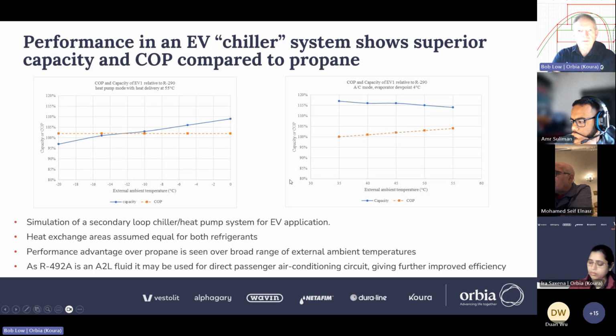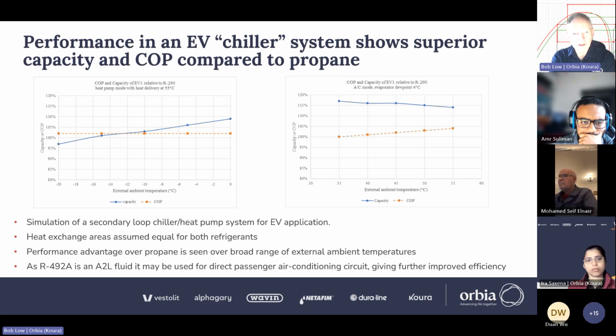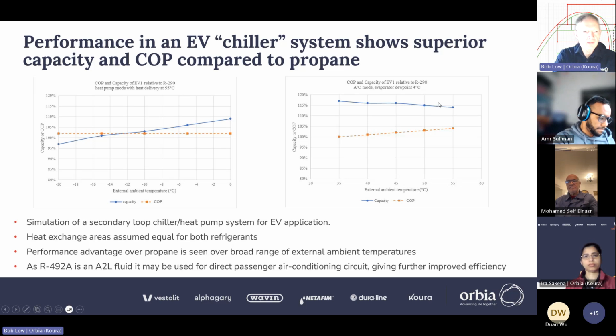So if we then take that concept and apply it to some of the thermal management systems, the car guys need air at 50C for the cabin, which means the water temperature, the heat sink temperature has to be at least 55C. The two graphs here are the effect of ambient temperature on capacity or COP. And the graphs here are baseline relative to propane. So on the left we have heat pump mode, -20C. We're predicting capacity about 97% of propane, basically the same as propane. And then actually the capacity climbs above that of propane as the ambient temperature warms up towards zero. And the COP is pretty much consistently just above that of propane.